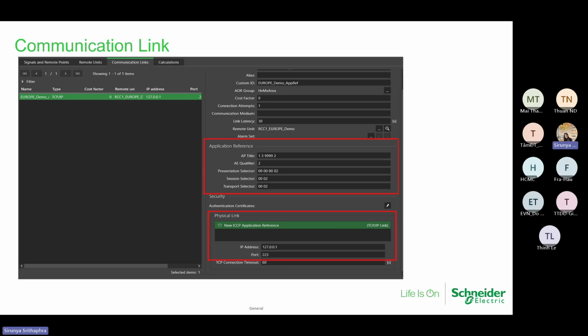But so for substation, we will not go with the IEC 104, right? Yes, but the existing communication from substation to our ADMS, so we have to create more channels to export the data to your system. We cannot connect directly from your system to the existing RTU and the substation.